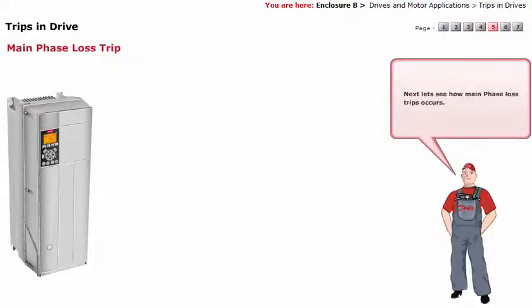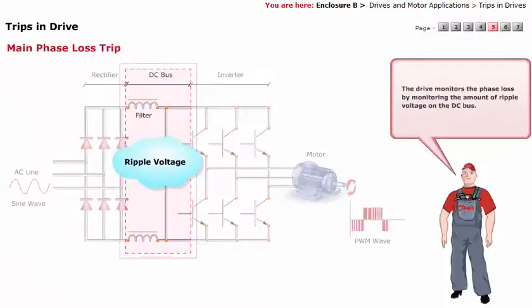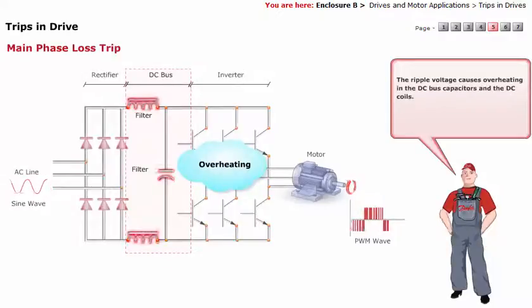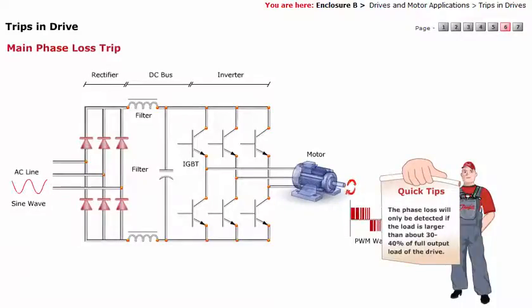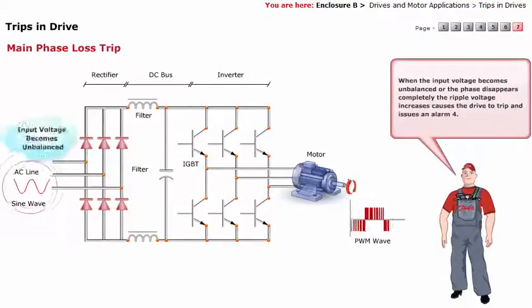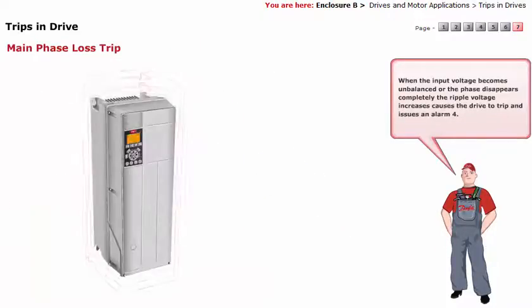Next, let's see how main phase loss trips occur. The drive monitors the phase loss by monitoring the amount of ripple voltage on the DC bus. Ripple voltage on the DC bus is the product of phase loss. The ripple voltage causes overheating in the DC bus capacitors and the DC coils. If left unchecked, the lifetime of the capacitors would be drastically reduced. Phase loss will only be detected if the load is larger than about 30 to 40% of full output load of the drive. When the input voltage becomes unbalanced or the phase disappears completely, the ripple voltage increases, causing the drive to trip and issuing alarm 4.